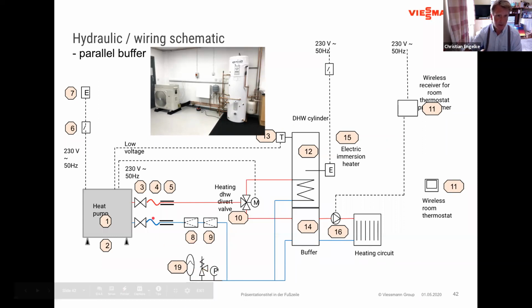So that's very simple. The wiring side of it, we have here obviously the electrical power supply with an isolator switch, which is shown here. And then we have the low voltage temperature sensor going back to the outside unit and the 230 volts power supply for the 3-port valve. These are really the only electric components you need to wire into the outside unit.